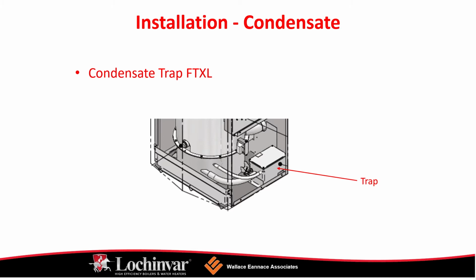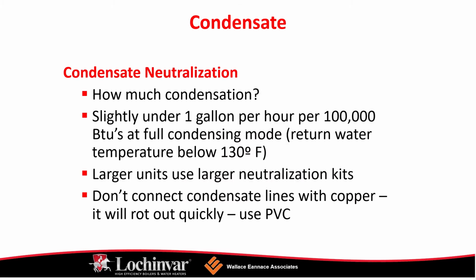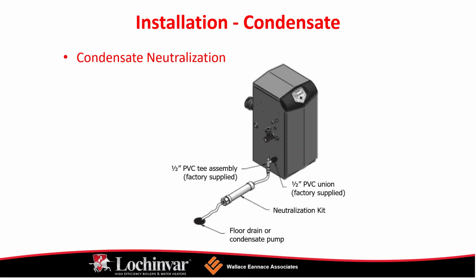Condensate. Installation and condensate. So we certainly want to use the condensate trap. This is pretty much what you'd see coming along with a Knight boiler. Drains to a floor drain. On our FTXL boiler, which a few slides back I mentioned was for large residential or light commercial, we have a condensate trap built into the unit.